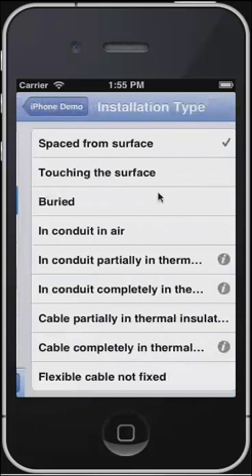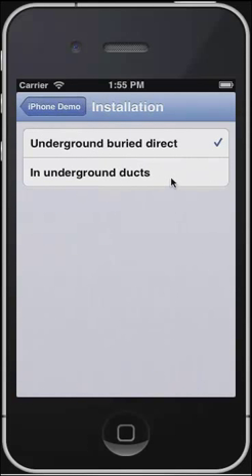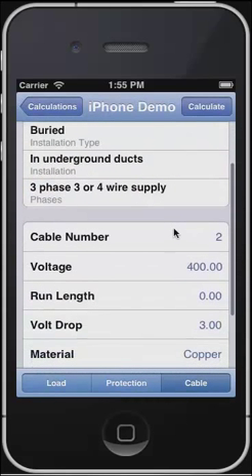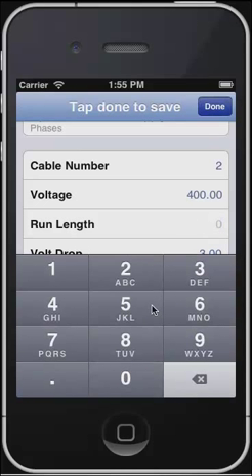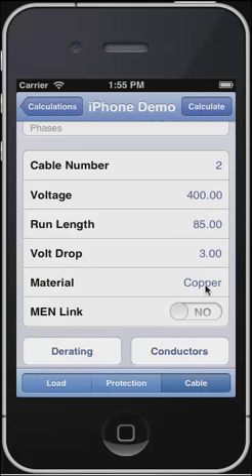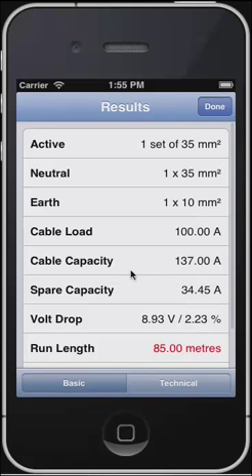We can also enter how the cable has been installed — it's going to be buried, and buried in conduit. We also enter the run length of this calculation, the volt drop required, which we've set at 3%. From this screen we can also put in additional derating conductors. We now hit calculate.